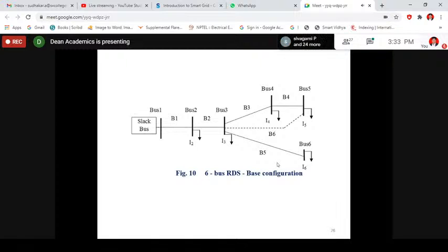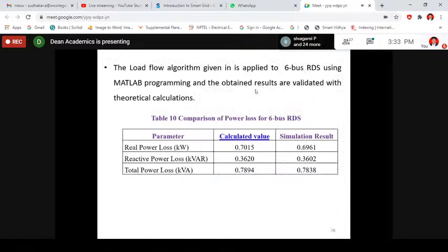The radial distribution system has a different load flow solution technique, because the R/X ratio is higher than conventional, making the Newton method non-convergent. So a separate distribution load flow solution is used—this is popular, and our research scholar developed MATLAB programming for it about 5 years ago.